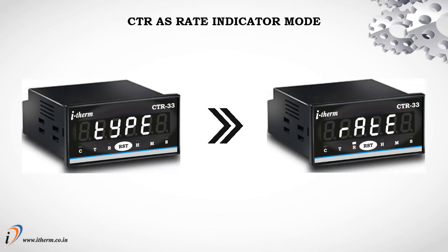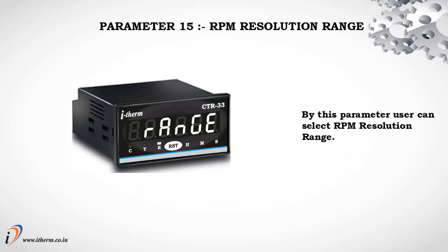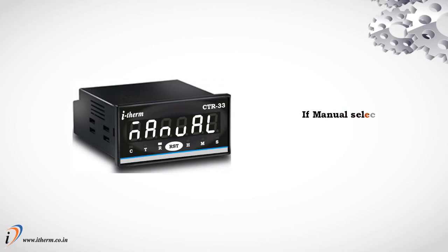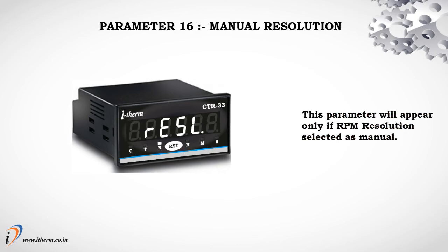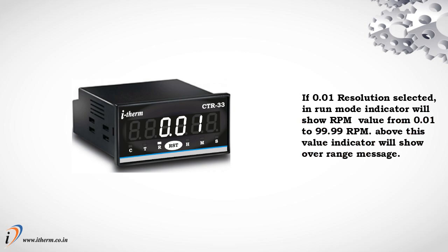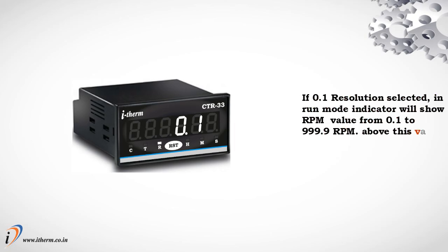CTR as rate indicator mode. Parameter 15: RPM resolution range. By this parameter, the user can select the RPM resolution range. If auto is selected, RPM resolution will change automatically. If manual is selected, the user can select a particular RPM resolution. Parameter 16: Manual resolution — this parameter appears only if RPM resolution is selected as manual. If 0.01 resolution is selected, the indicator will show RPM values from 0.01 to 99.99 RPM; above this value the indicator will show an over-range message. If 0.1 resolution is selected, the indicator will show RPM values from 0.1 to 999.9 RPM; above this the indicator will show an over-range message.